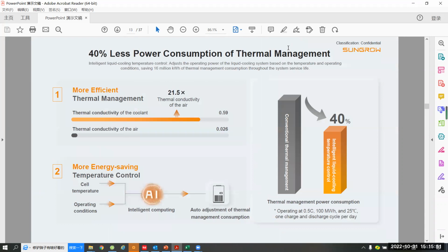The PowerTitan system uses an advanced liquid cooling solution to cool and balance the temperature of the lithium battery. It has many advantages. First, compared with air, the thermal conductivity of the coolant is 21.5 times higher. We also use AI technology to detect cell temperature and control the running power of the cooling system. Compared with traditional thermal management, the power consumption of liquid cooling can decrease by 40%, resulting in lower cost and better benefits.